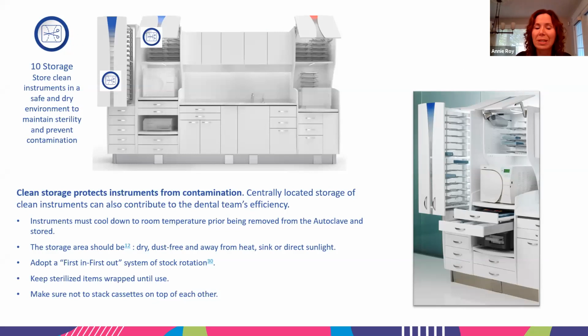Adopt a first in, first out system of stock rotation, and keep sterilized items wrapped until use. Make sure not to stack cassettes on top of each other. Some storage setups only have shelves or wire mesh baskets, so you end up having to stack them. This isn't ideal, because we want to keep those instruments dry and remove excess moisture that may remain from the sterilization process.